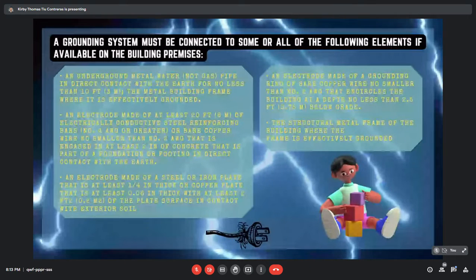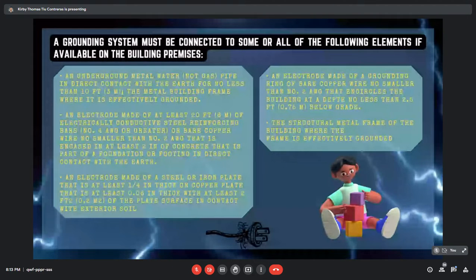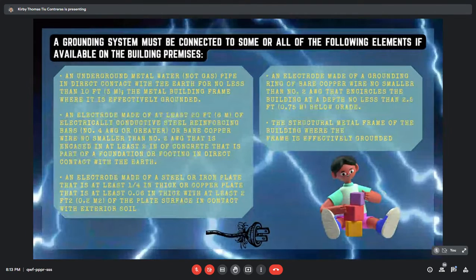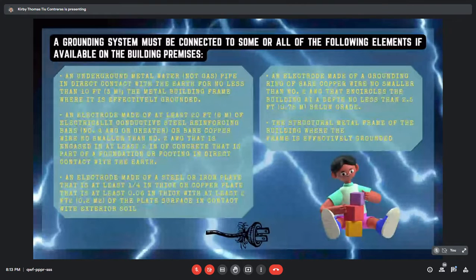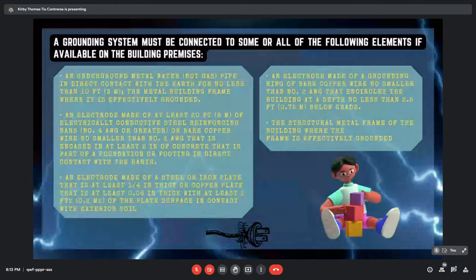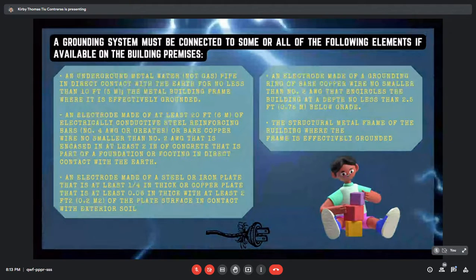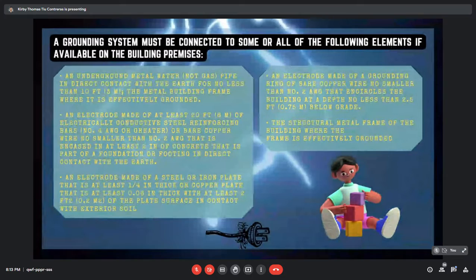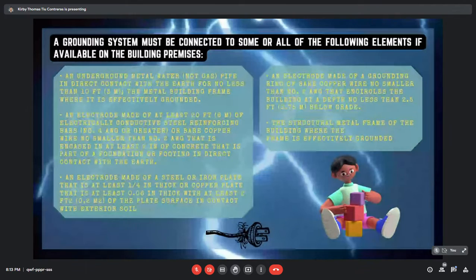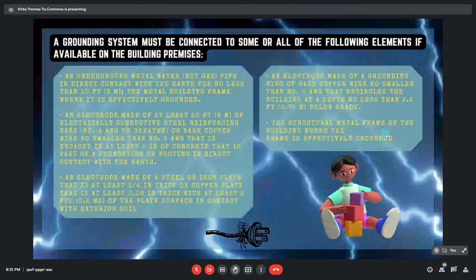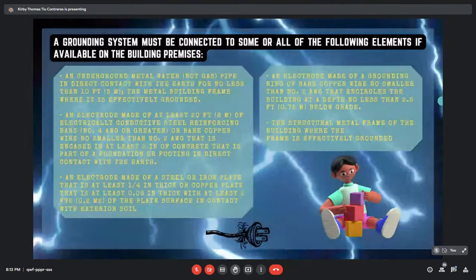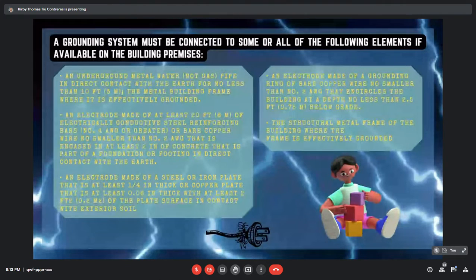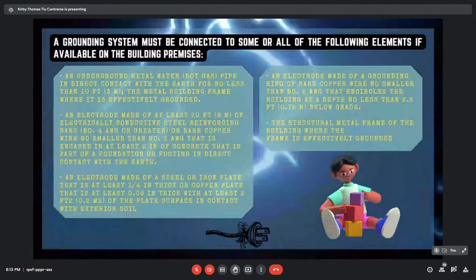And next, an electrode made of a steel or iron plate that is at least 1/4 inch thick, or a copper plate, with at least 2 square feet of plate surface in contact with exterior soil. Now, next is an electrode made of bare copper wire no smaller than 2 AWG that encircles the building at a depth of no less than 2.5 feet below grade. So, the structural metal frame of the building where the frame is effectively grounded. Okay, next please.